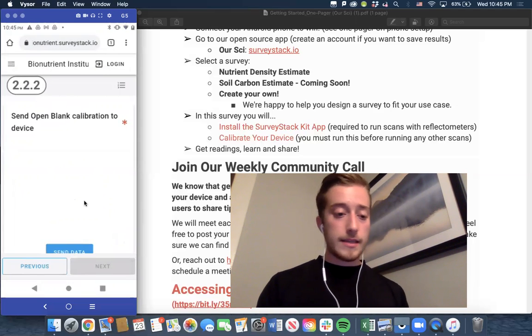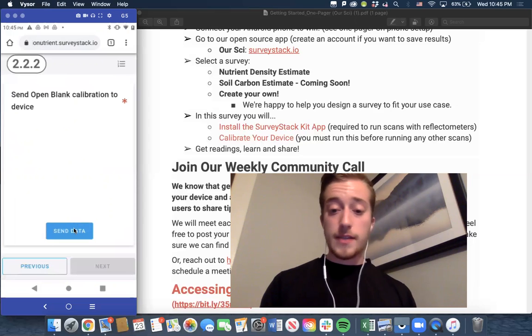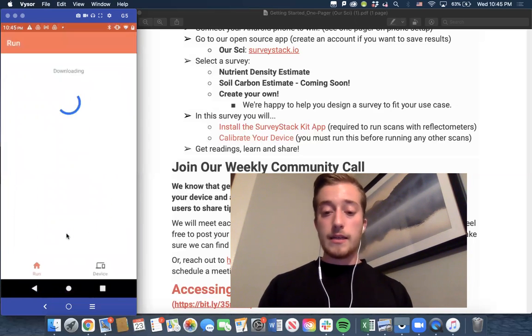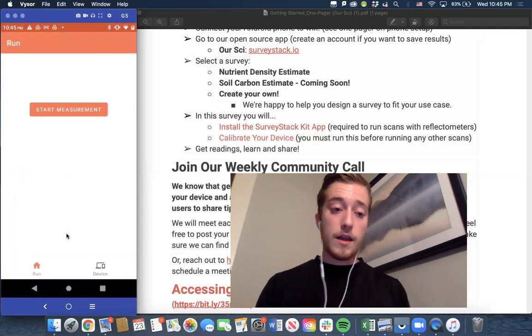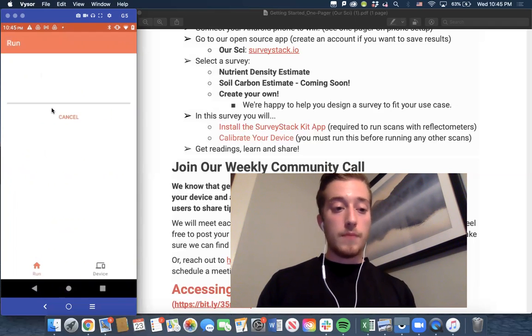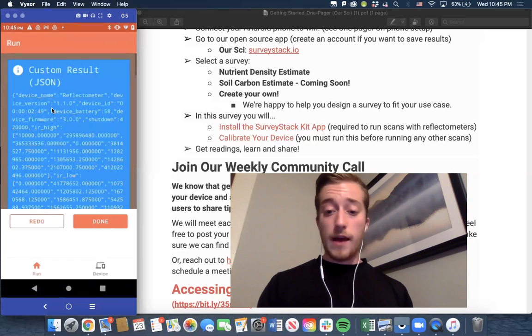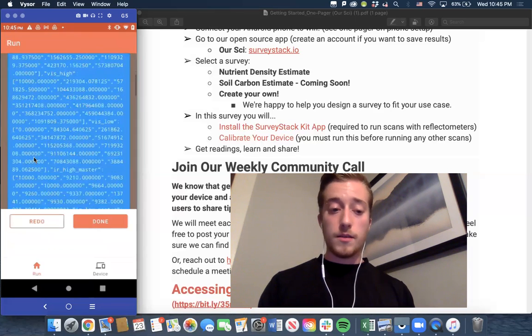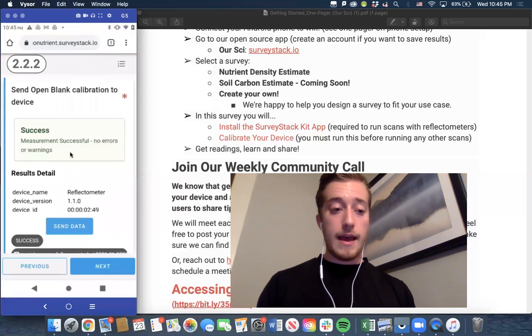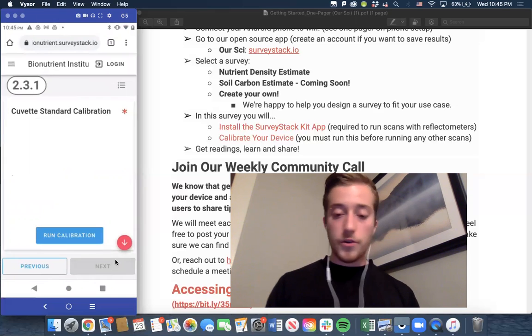The next command is just sending data to device. There are no special instructions. Just click send data, and it's going to send that last scan to your device. So start measurement. The LEDs don't flash. It will just come up with this blue JSON custom result, and you can click done, and again get your success. Click next, and now your cuvette standard calibration.